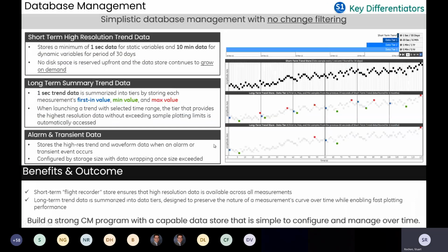Speaking of storage, with the move from System 1 Classic to System 1 EVO, we moved from Microsoft SQL Server to now we are using a PostgreSQL database. We found that Microsoft SQL Server gets unstable when we get up to about 300 gigs of stored data for this high speed in and out rolling data. And so moving away from that, we moved to Postgres, which is happy with terabytes and petabytes of data.